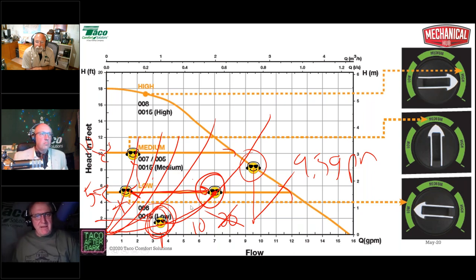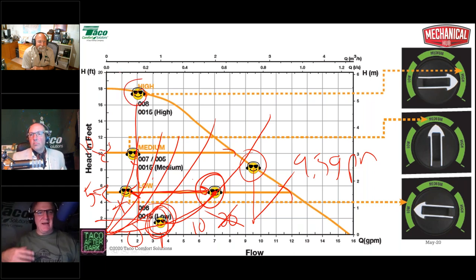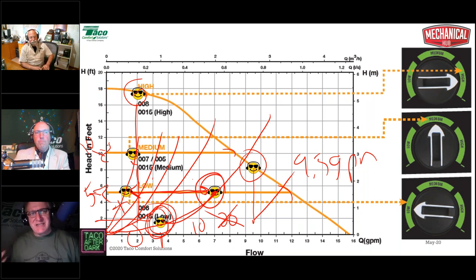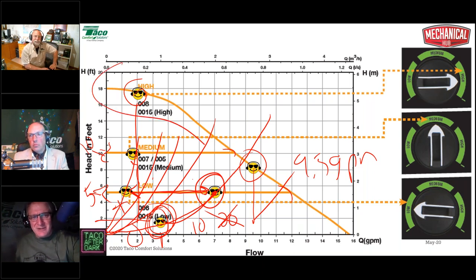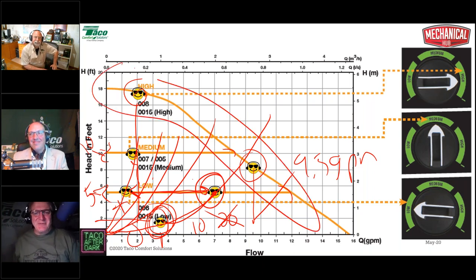It's certainly not bad. Alrighty, and if we said, I don't know what I'm going to do, I'm just going to turn it all the way up and get out of here. Well now, 2 gallons a minute, in terms of delta T, I'm no different than where I was before with the fixed speed pump. The only difference is I'm going to use about half the watts, all right? So I'm in electrical savings mode, but I'm not doing my system any favors. Nope. See, folks, this is why we don't call them smart pumps, because that's not that smart, okay? That's why we don't call them smart pumps. They are interesting pumps. They are compelling pumps, but they're a far bit away from smart in my book.